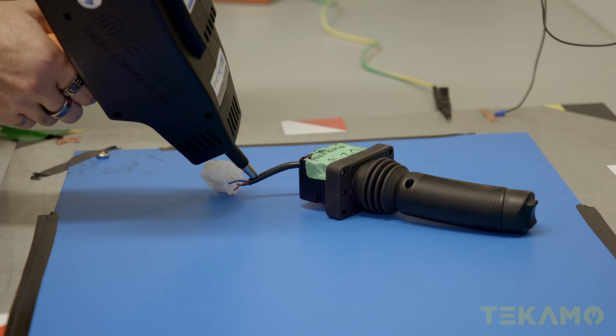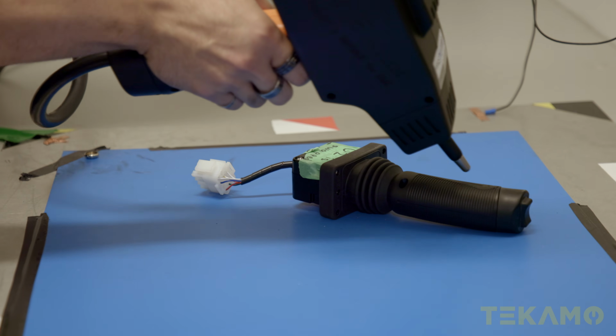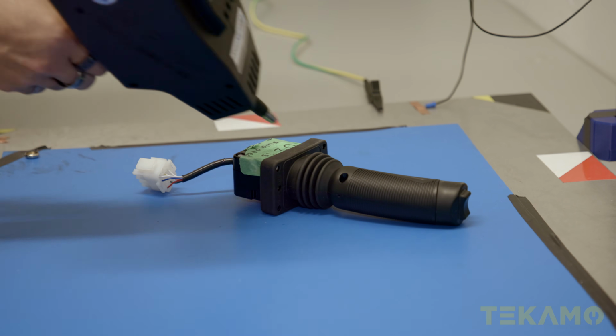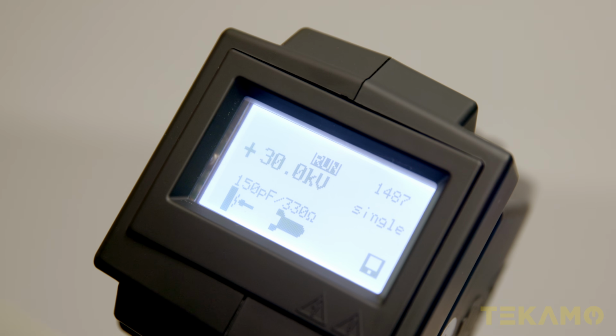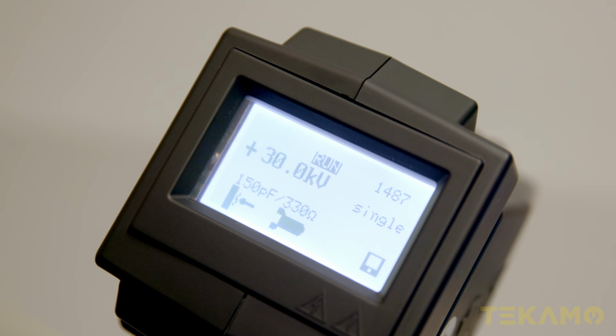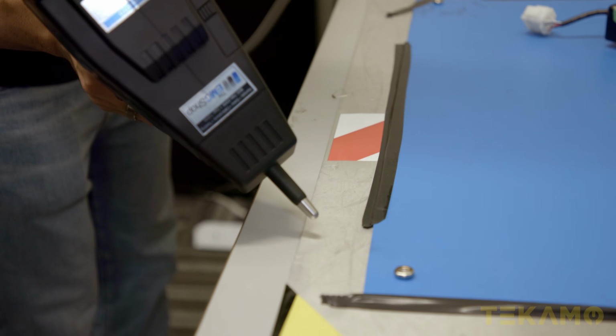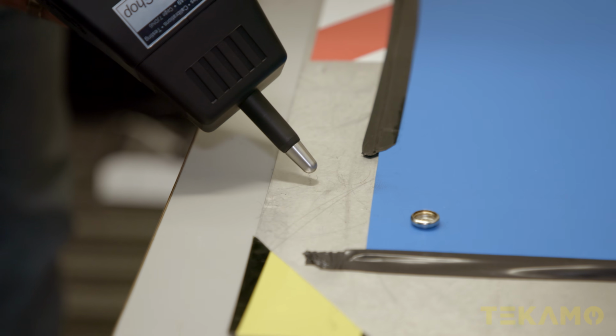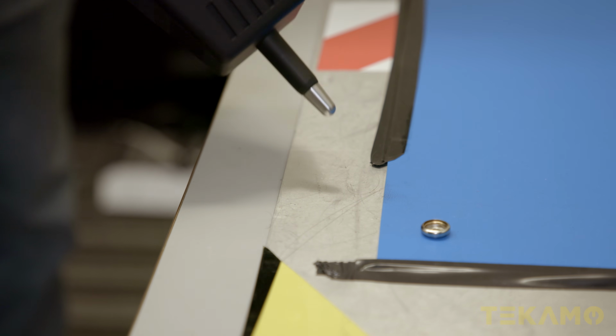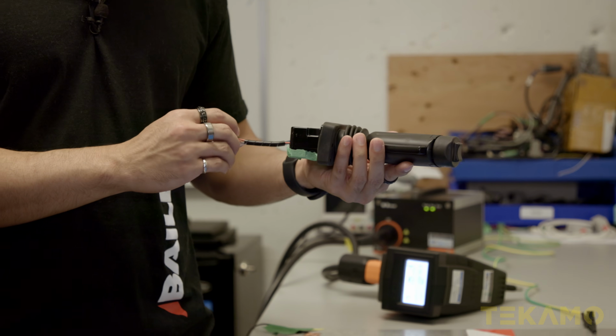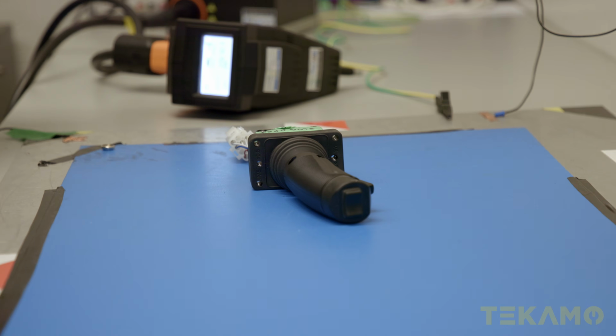We can scan our product to see if it discharges anywhere. This tester can go all the way to 30 kilovolts. When our body generates electrostatic discharge, it's a very high voltage but a very short period of time. So we can control and simulate how touching one of our products would behave, and see if the product would break or fail under that specific discharge.